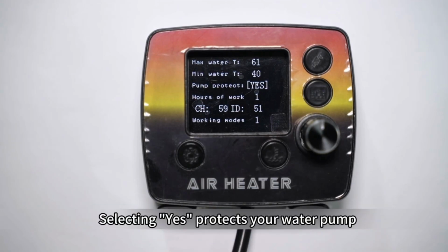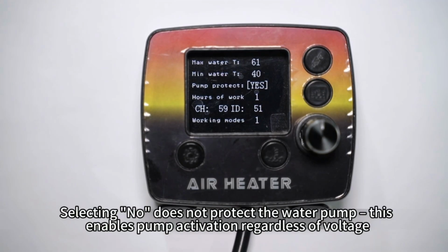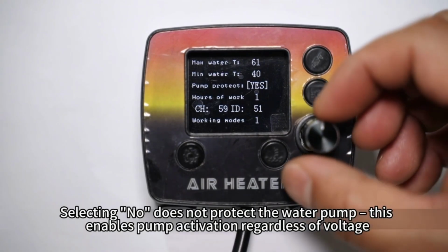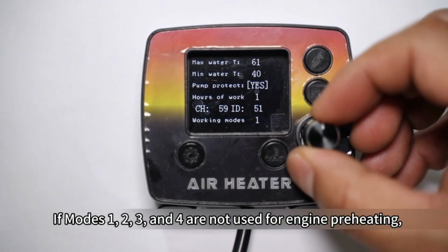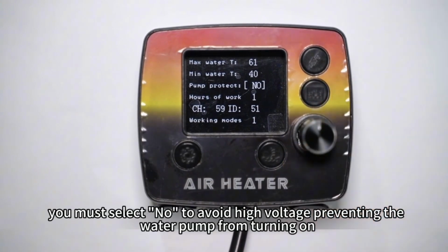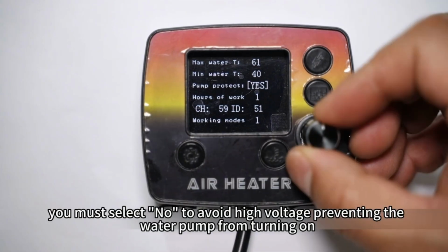Selecting yes protects your water pump. Selecting no does not protect the water pump. This enables pump activation regardless of voltage. If modes 1, 2, 3, and 4 are not used for engine preheating, you must select no to avoid high voltage preventing the water pump from turning on.